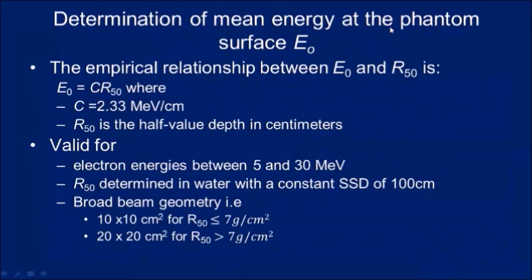Determination of the mean energy at the phantom surface E0 is straightforward: E0 = C × R50, where C = 2.33 MeV/cm, an empirical constant. For example, if R50 = 4 cm, then E0 = 4 × 2.33 = 9.32 MeV. This equation is valid for electron beams of 5 to 30 MeV, and requires R50 measured at 100 cm SSD with the appropriate field size.